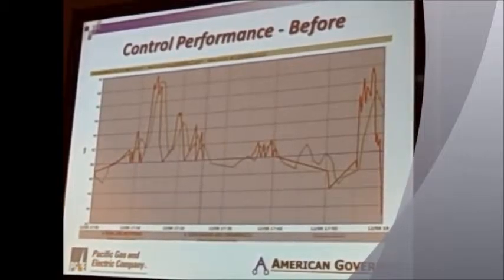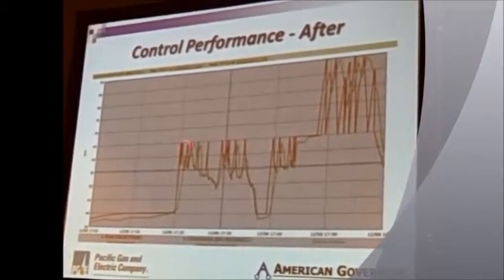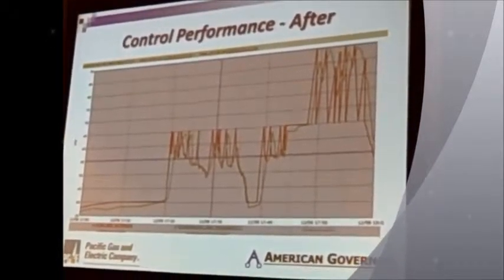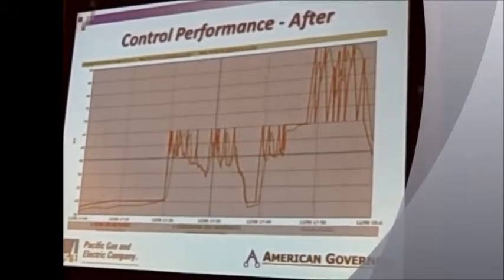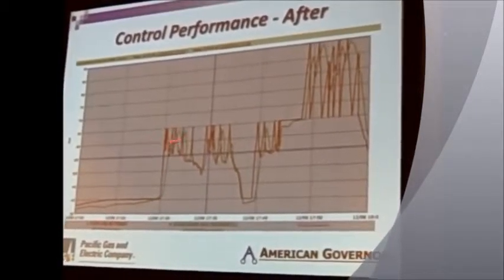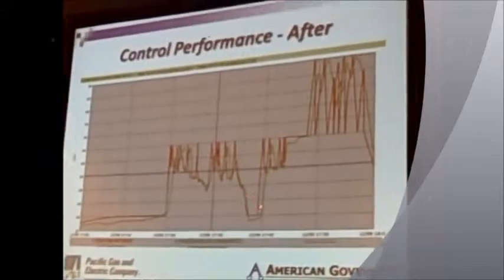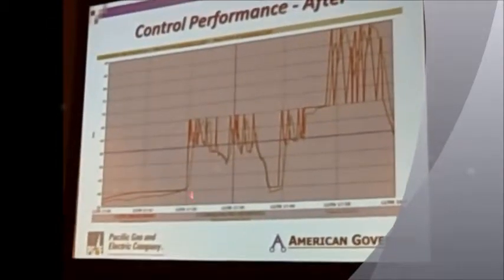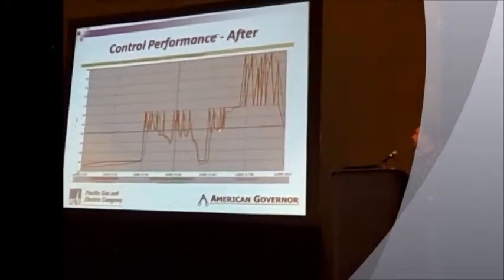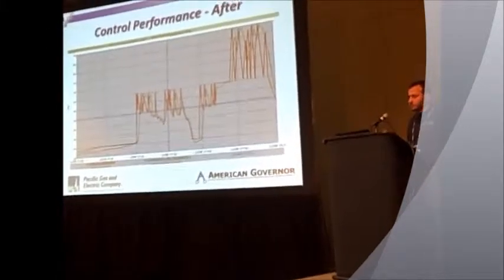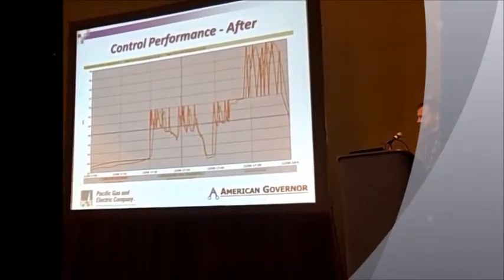Now, with the new governor control, you are still going to see some lag due to the natural rate that the unit can load up on, but that lag has been decreased. What you'll also see is no areas where the megawatts are not moving towards the set point. They're always tracking as accurately as possible. And that, again, is limited by the rate of change of the servo motor stroke.